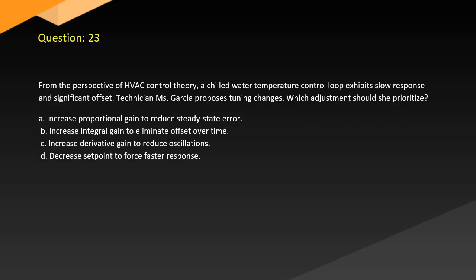Question 23. From the perspective of HVAC control theory, a chilled water temperature control loop exhibits slow response and significant offset. Technician Ms. Garcia proposes tuning changes. Which adjustment should she prioritize? A. Increase proportional gain to reduce steady-state error. B. Increase integral gain to eliminate offset over time. C. Increase derivative gain to reduce oscillations. D. Decrease set point to force faster response.